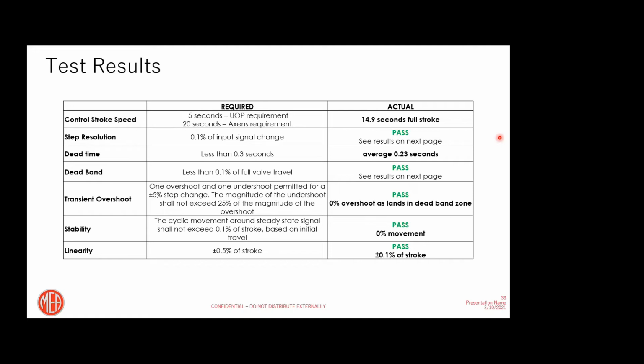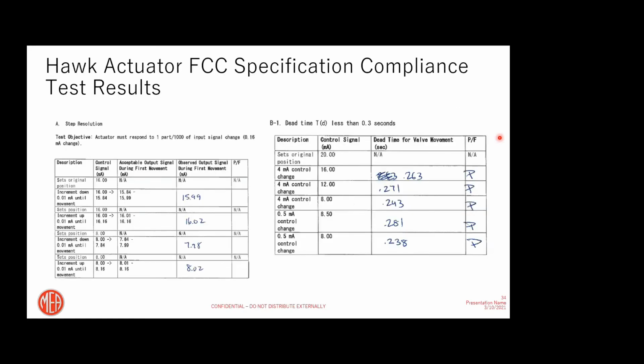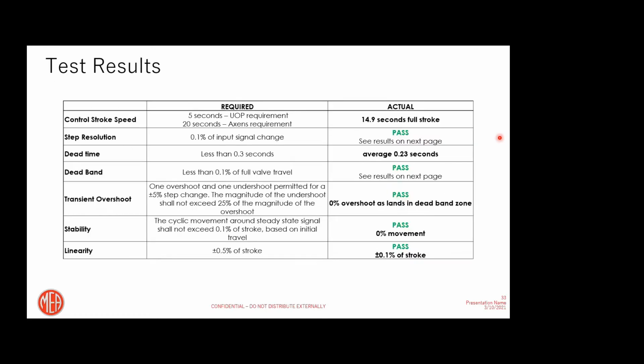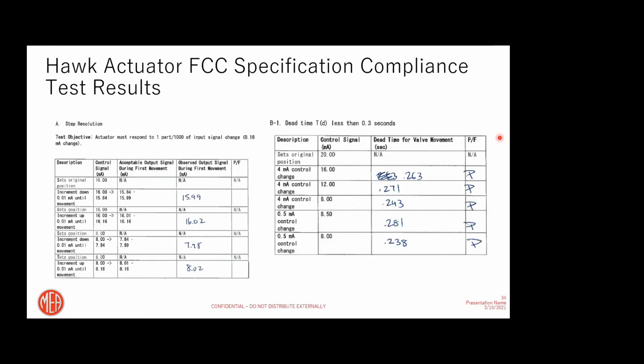Linearity actually was plus or minus 0.1% of the stroke. After that, we didn't just run the test. We actually built 4 units and did the FAT testing in front of the customer. These are actual results from each test, which was witnessed by the end user, and they actually saw all the performance of the actuator, also under load.